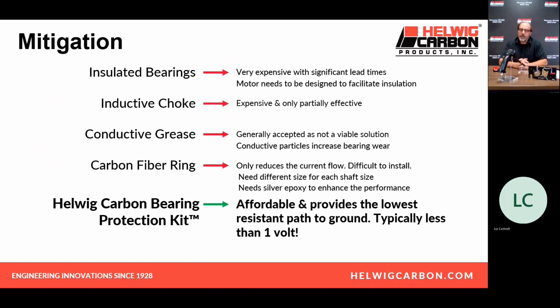It is not. A very common mitigation solution out there is the carbon fiber ring. This is an effective device, especially initially, and it does take the voltage and reduce it. It certainly does, but many times it does not bring it below the acceptable 2-volt level after a short period of time. Initially, I think you'll find it does, and it works well. But after just several months, I think you'll find that the contact force reduces. And if the contact force reduces, the voltage on the shaft increases, and the likelihood of a bearing discharge also increases.